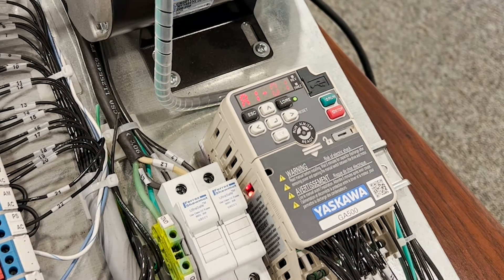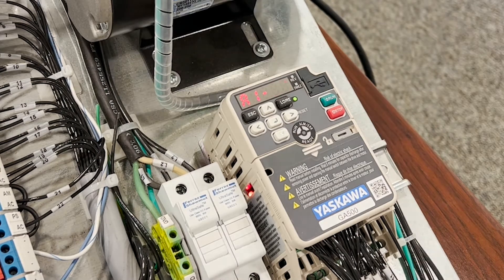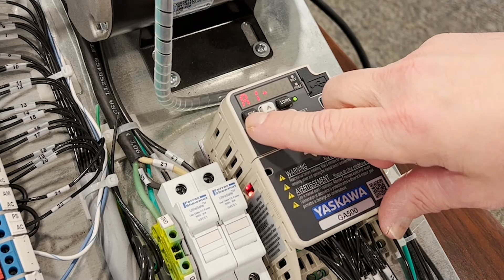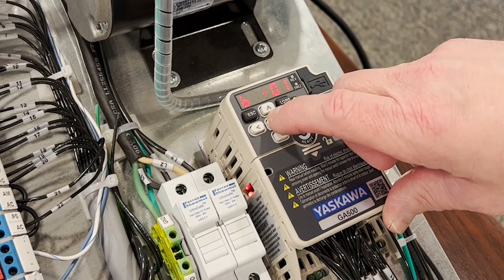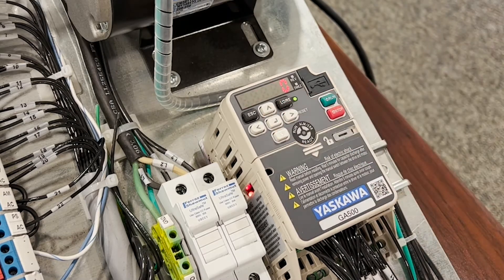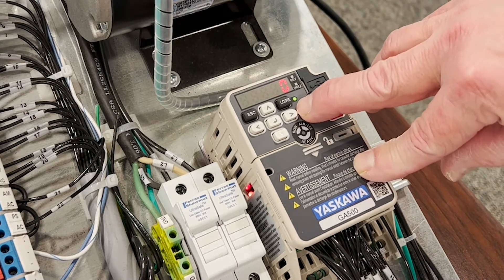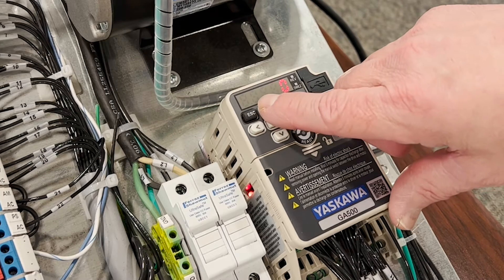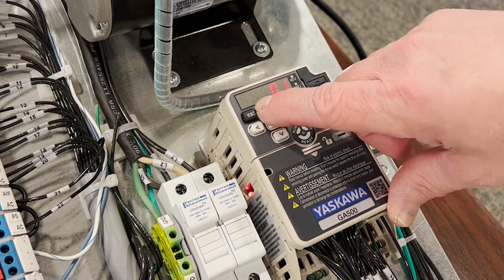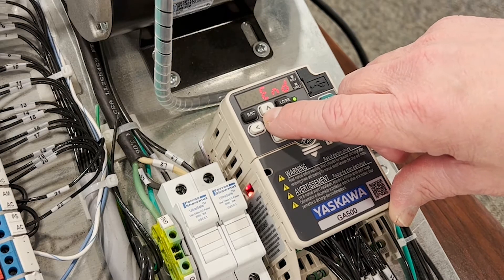Next we need to consider our reference source — how we're going to tell it how fast to run. That is parameter B1-01. A zero is going to be from the operator, which is where we want to run in this instance. But if you wanted to go to terminals — a wired speed pot — we would make it 01.